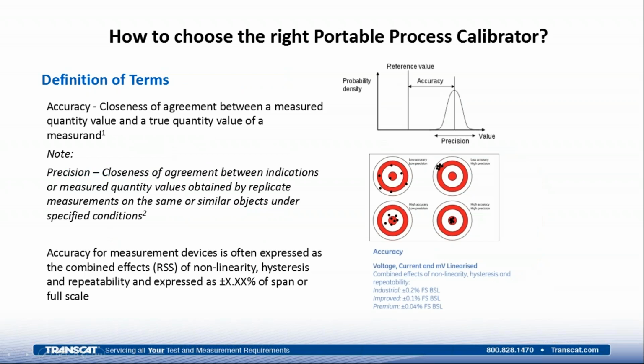So accuracy is actually the closeness of agreement between a measured quantity value and a true quantity value of a measurand. So if we look at our graphic, our illustration there, we have the average or mean or median of a number of different values that will fall within a bell-shaped curve distribution, standard distribution. And the mean or median of that average when compared to the reference value, the calibrator or the standard, is commonly called the accuracy. Note that the precision is the closeness of agreement between indications or measured quantity values obtained by replicate measurements on the same or similar objects under specified conditions. So that's kind of the spread or distribution of those measurements when compared to each other.